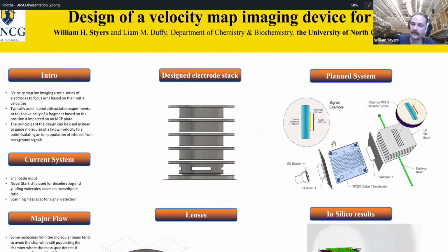What this is able to do is it behaves similar to a quadrupole for a mass spectrometer, only it is an array of them with very small spacing between to produce very high electric fields. The way a quadrupole is oriented, we have something akin to this where each of these fingers here are electrodes. We are able to set potentials of each of these electrodes and cycle the potentials around the electrodes such that typically ions passing through it can be retained and separated from each other as it goes on.